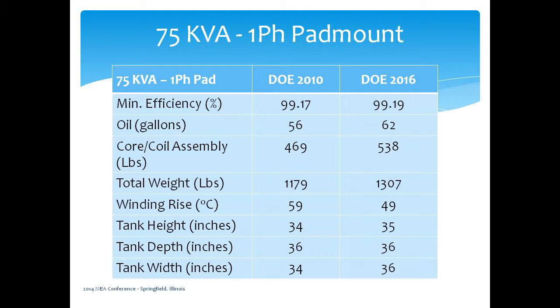I'm going to flip through these pretty quick because you're going to see the weight increase by 15%, which will impact the cost. We're trying to keep the size down too, but you can see generally these units are going to weigh way more. The core coil assembly is heavier - that's the engine, that's the cost of the unit. Typically it runs 70-80% of the cost of the unit is just the core coil assembly.